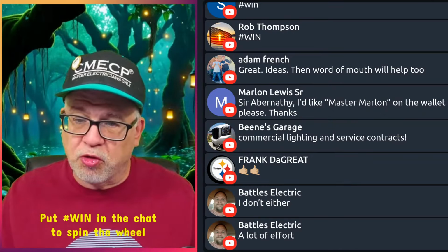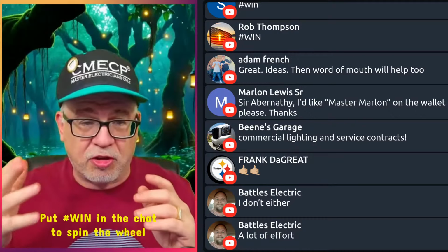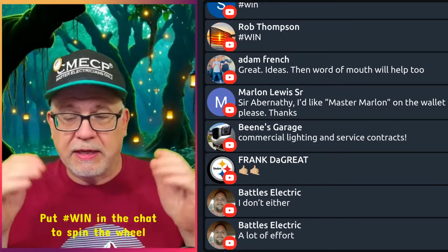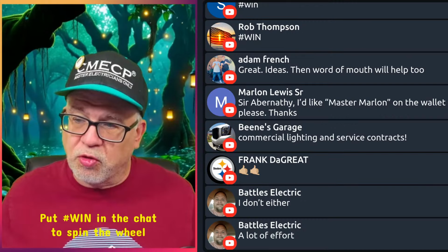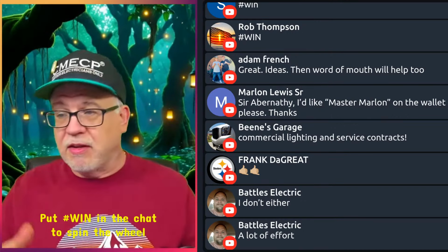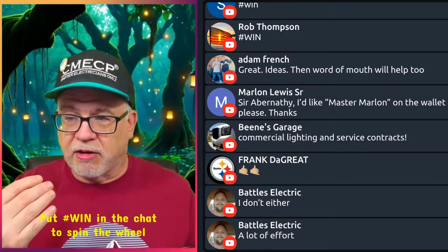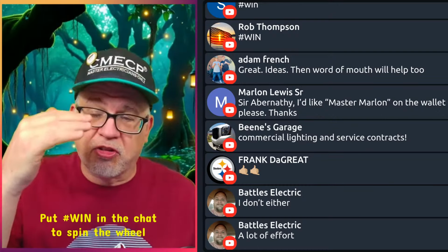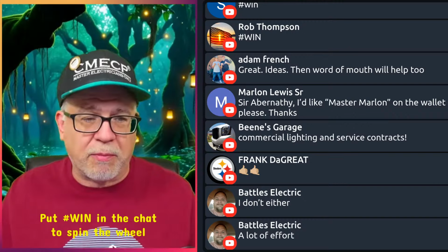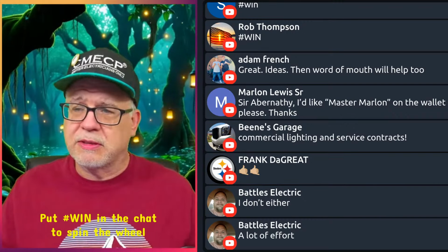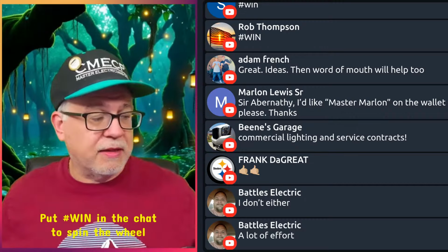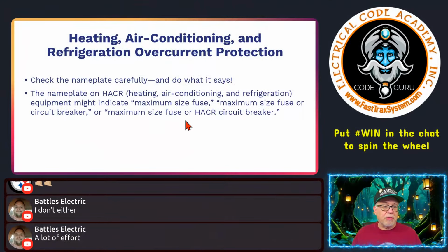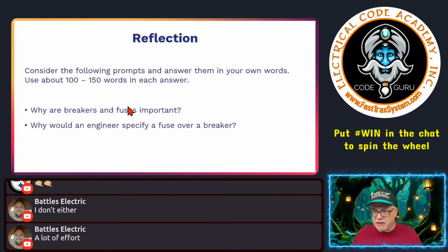If it says maximum size fuse or circuit breaker, then it doesn't matter. Then I leave the pull-out next to the unit and I use a circuit breaker that's back at the panel. That's fine. If it says maximum size fuse or HACR breaker, then all you're doing is using a breaker that is designed to be used in an air conditioning application. It understands that volatile inrush. It's designed that way. I think most of the breakers today, circuit breakers, are going to be HACR rated anyway. So again, this allows you to use a circuit breaker or a fuse in this protection. This allows only fuses. This allows circuit breaker or fuse. All based on what's written on the nameplate on the side of the HVAC unit, okay? All right?